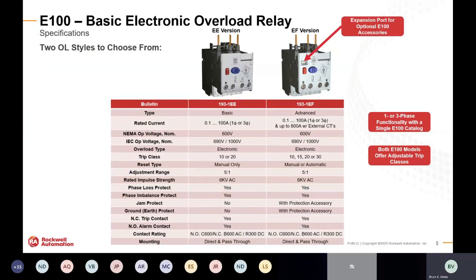If we look at the two different versions of the E100, very similar to that of the E1 Plus, you have what's referred to as the basic version and the advanced version. If you compare the basic version to the E1 Plus overload relay, it used to only offer a fixed trip class of 10. Well, now the basic version of the E100 actually offers an adjustable trip class of 10 or 20. Something that we got a lot of good feedback from customers on, asking for an adjustable versus a fixed trip class. So something to keep in mind there.